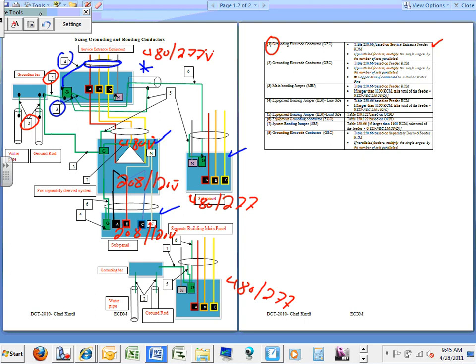How do you bond it? It's called equipment bonding jumper, line side. Why do you guys think it's line side? Look at that: line side, because the overcurrent protection device, the main, is on the line side of the main. The main is right here, and it's on the line side of the main. How do you size this one? Exactly like the equipment bonding jumper, the system bonding jumper or main bonding jumper. Can you guys see that? 12.5% if it's more than 1100 kcmil.